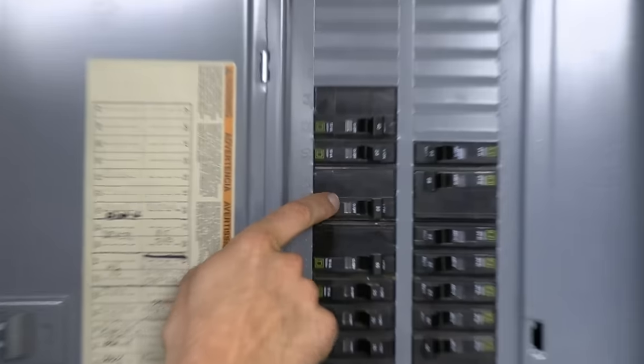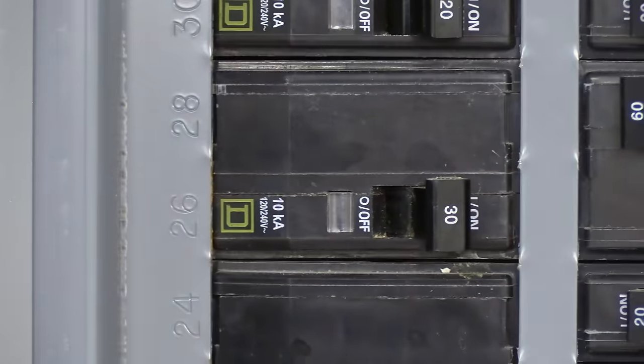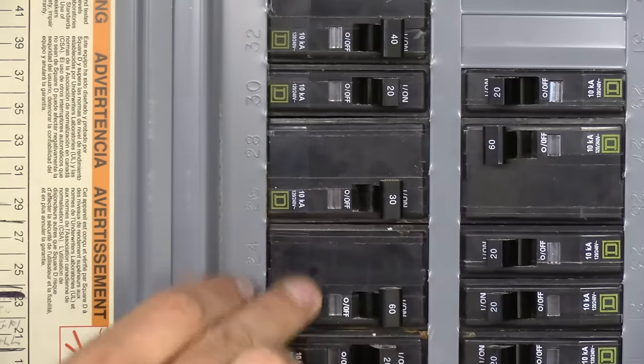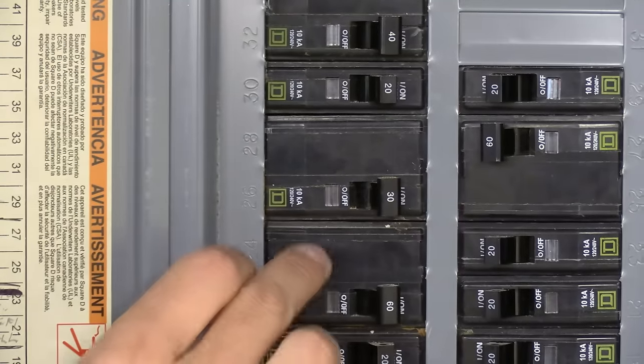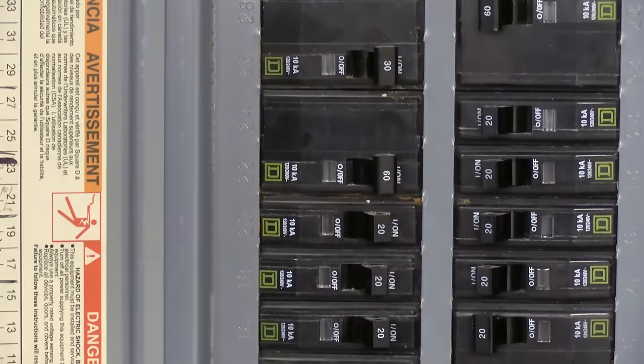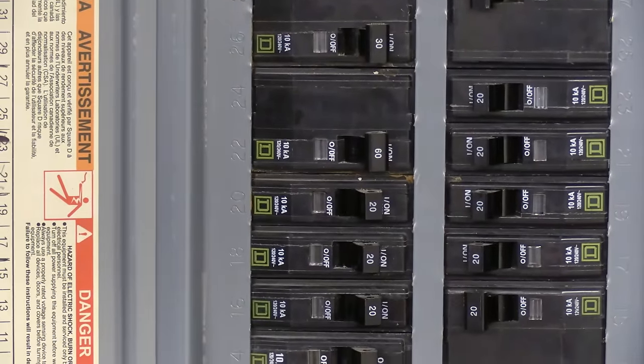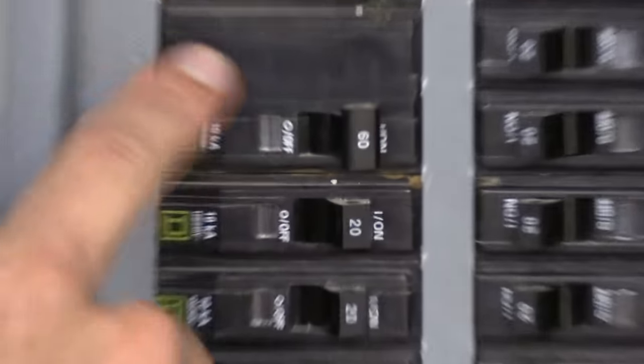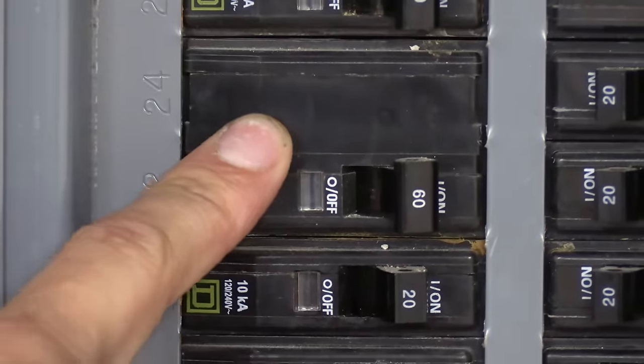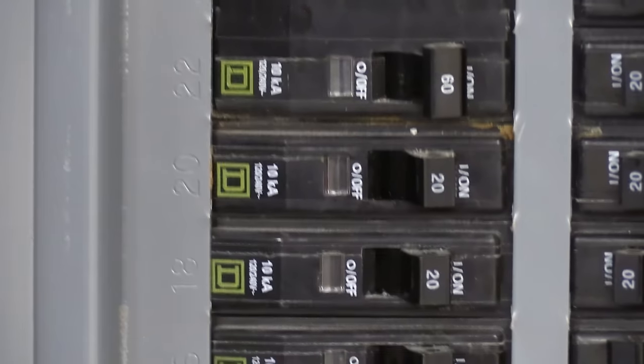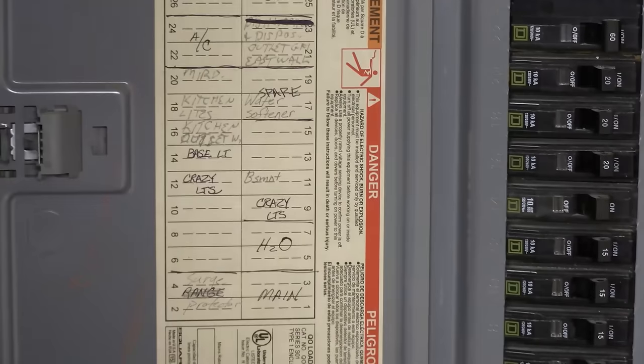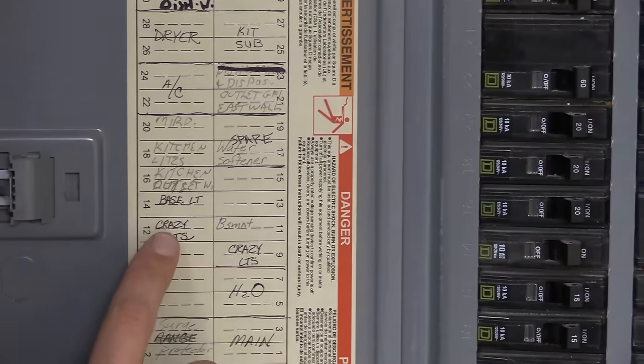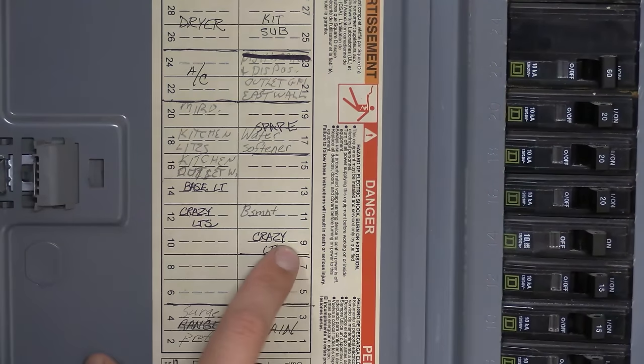Two pole 30 amp breakers like this are typically water heaters and air conditioners. Two pole 60 amp breaker like this might be a sub panel. It could be an air conditioner. And in fact, I've got a large air conditioner sitting outside here. So I'm suspicious that that might be the one. It is labeled AC, but I'm suspicious of all of these labels because we've got crazy lights, crazy lights.